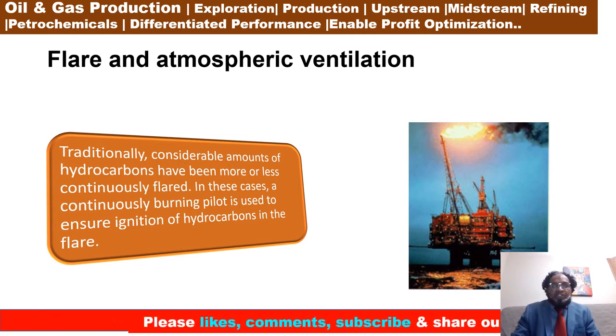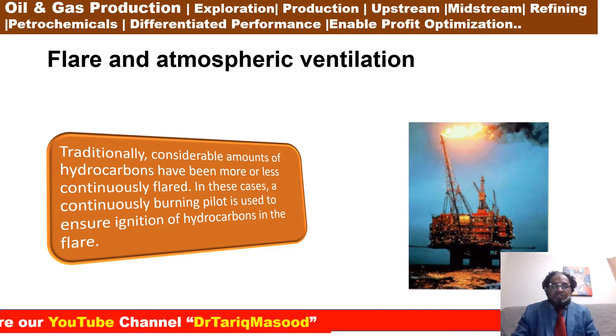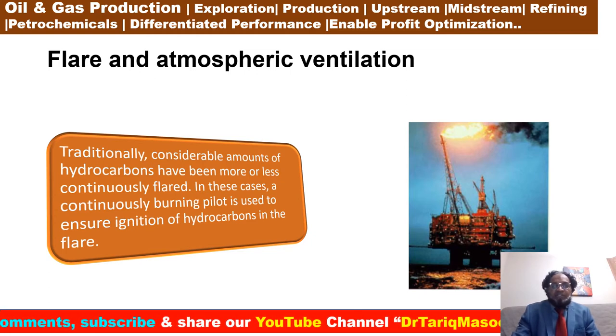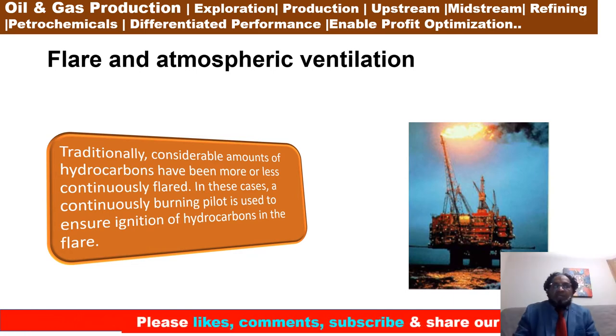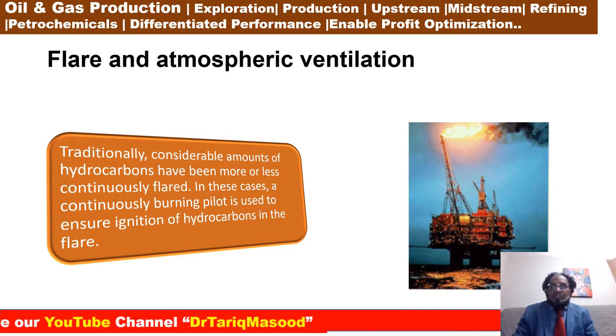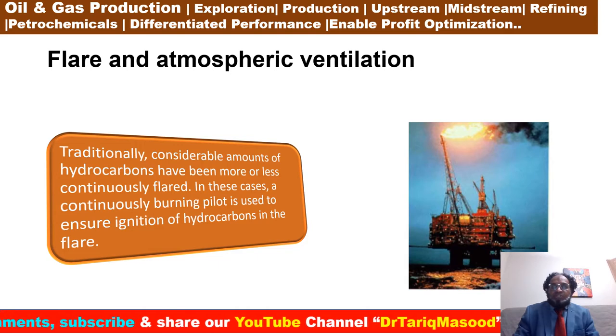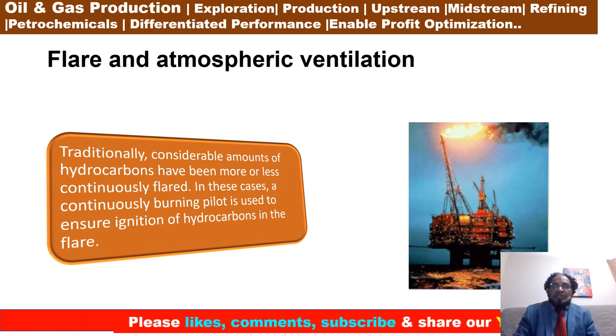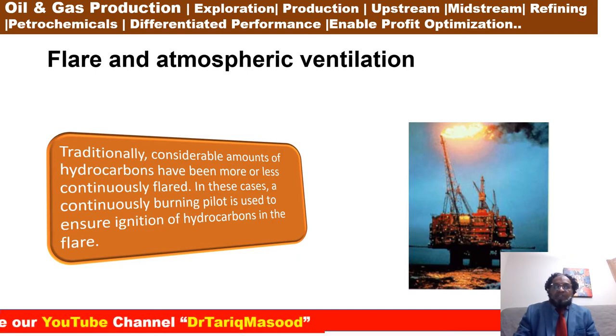Okay. Traditionally, a considerable amount of hydrocarbons has been more or less continuously flared. In these cases, a continuous burning pilot is used to ensure ignition of hydrocarbons in the flaring systems. Stronger environmental focus has eliminated continuous flaring in many areas. Vapors and flare gas are normally recovered, and only in exceptional situations does flaring occur. To avoid the pilot flame, an ignition system is used to ensure a safe ignition even when large volumes are discharged. One patented solution is a ballistic ignition system which fires burning pellets into the flare gas flow.